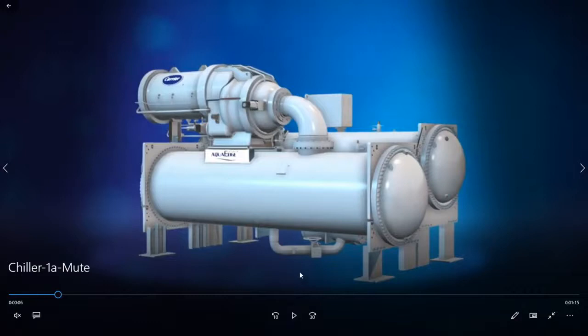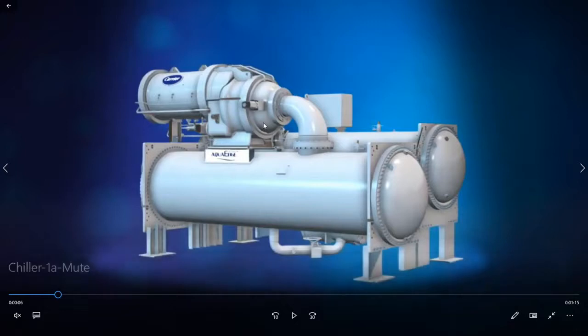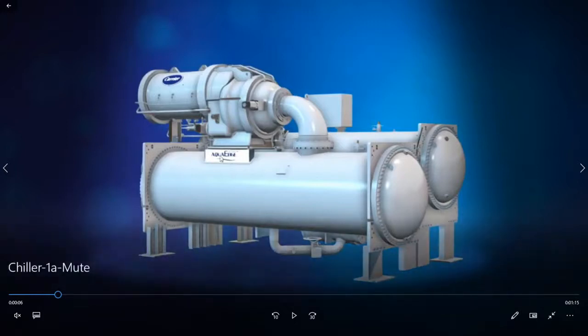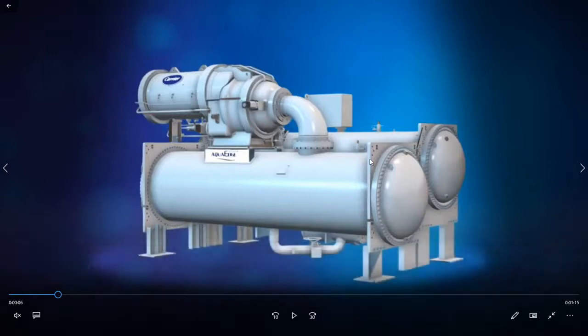Now if you look at this figure, this is a typical chiller, and over here we have the compressor. So this is actually the compressor if you focus on the cursor, and this is the motor which is driving the compressor. And remember, the inlet to the compressor is from the evaporator. So this vessel over here is a shell and tube heat exchanger, which is the evaporator in this particular application.